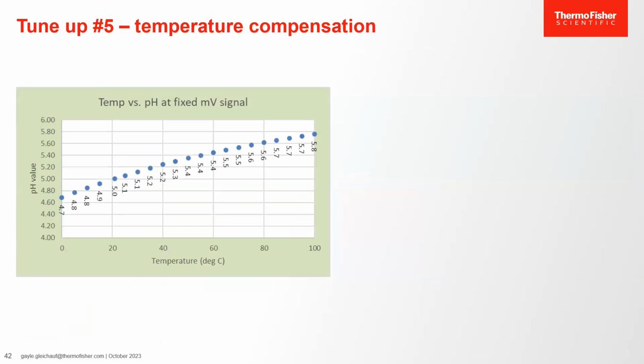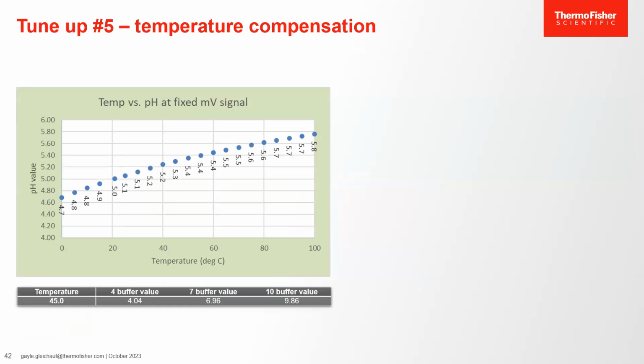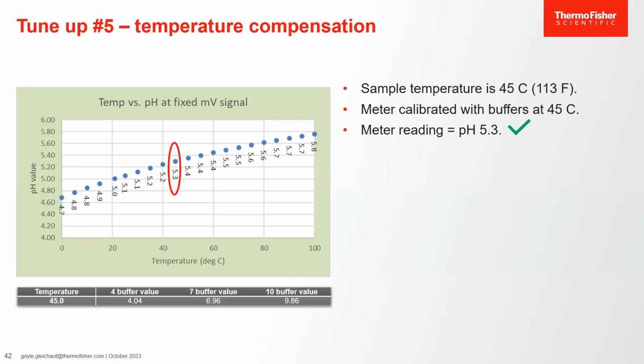Here's an example. If I don't have temperature compensation, I have to calibrate and test samples at the same temperature to get accurate results. If my sample's at 45 degrees C, I may put my buffers in a water bath and equilibrate them to 45 degrees C. Then I calibrate pH, making sure that the correct buffer values at 45 degrees C are assigned. When I measure my sample, it reads 5.3. This is a good result.